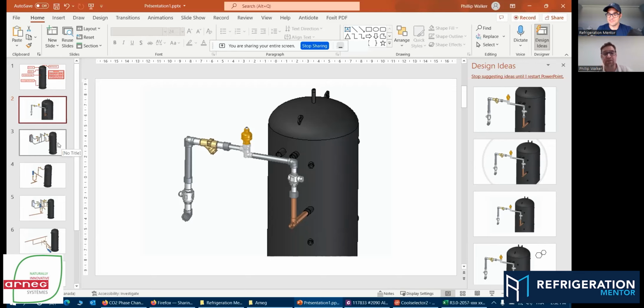And we can't forget as well, cooler environments, drier environments, we have a lot less latent load for infiltration for the display cases. So Arneg provides display cases as well. And our maintenance on our suction temperature is far easier throughout the winter season, because the store environment is much drier. We're at a very, very low dew point. So there's a lot less infiltration or vapor pressure migration for the display cases. So suction maintenance is much easier. And we've said, hey, we can move that over to maybe keep this flash tank full, move it to a secondary flash tank with a smaller valve, because we need less mass flow. And the success has been outstanding in terms of that.